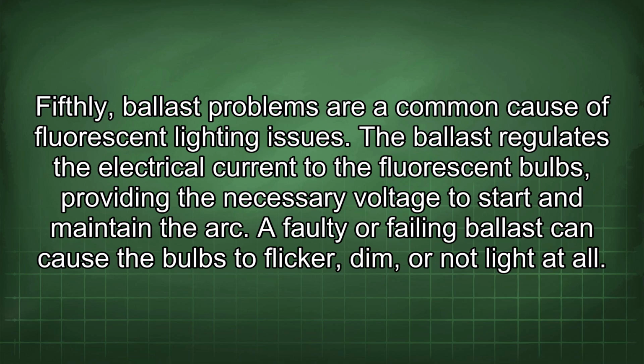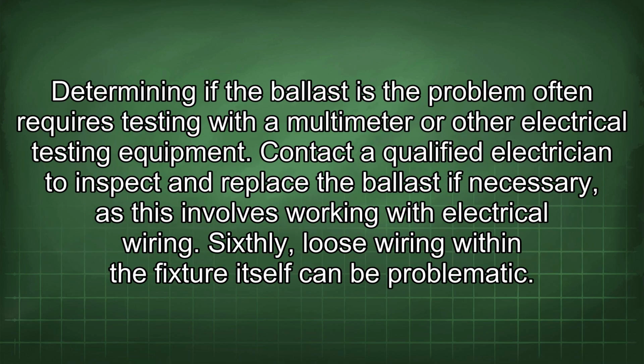Fifthly, ballast problems are a common cause of fluorescent lighting issues. The ballast regulates the electrical current to the fluorescent bulbs, providing the necessary voltage to start and maintain the arc. A faulty or failing ballast can cause the bulbs to flicker, dim, or not light at all. Determining if the ballast is the problem often requires testing with a multimeter or other electrical testing equipment. Contact a qualified electrician to inspect and replace the ballast if necessary, as this involves working with electrical wiring.